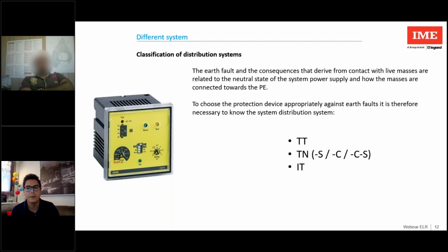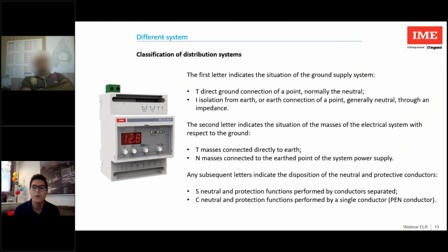As we see described in this slide, each letter indicates something. For example, the first T indicates the direct connection of earth to a point, generally the neutral. The I indicates insulation from earth or connection to ground through an impedance. The second letter indicates how the masses are connected to the earth. The subsequent letter indicates the status of the neutral and earth and how it is connected.